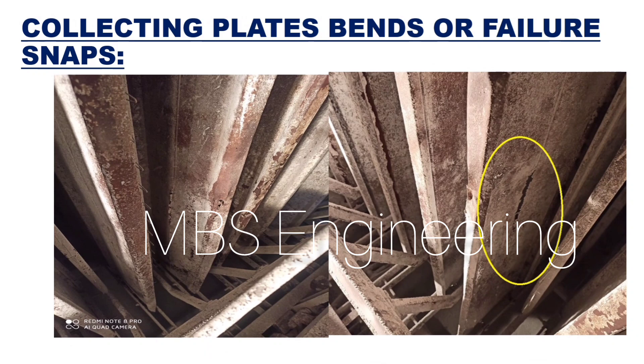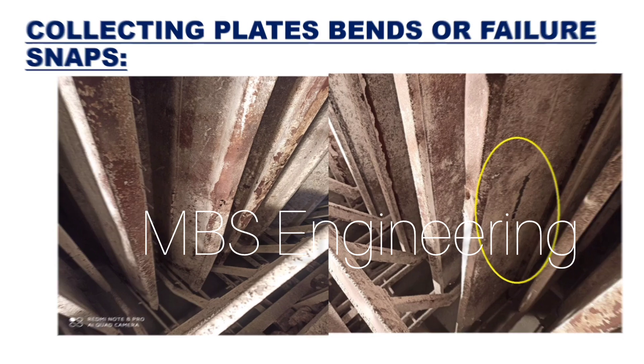Please refer to the collecting plates bends or failure snaps for a better understanding of collecting plates failure at the bottom of the collecting plates and its rapping bar portion. Those electrodes need to be replaced or repaired for further operation. Holes and damage observed over the collecting plates surface due to corrosion.